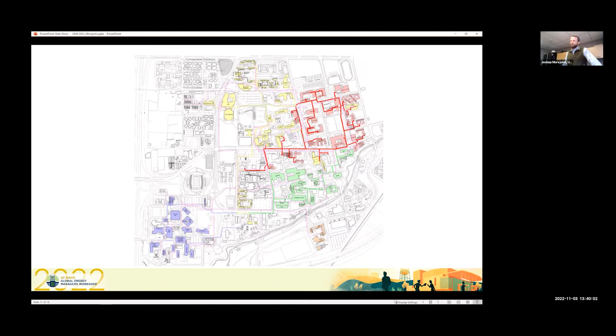The next phase is the yellow area shown here, which will get about the north half of the campus onto hot water, and also tie into the heat recovery chillers we're going to install at the chiller plant to replace our oldest two chillers. So another avoided cost there.